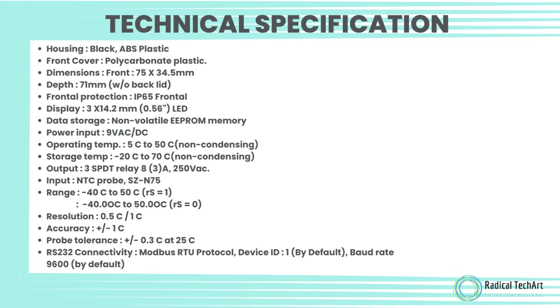Resolution: 0.5 degrees Celsius or 1 degree Celsius. Accuracy: plus or minus 1 degree Celsius. Probe tolerance: plus or minus 0.3 degrees Celsius at 25 degrees Celsius. RS-232 connectivity: Modbus RTU protocol. Device ID: one by default. Baud rate: 9,600 by default.